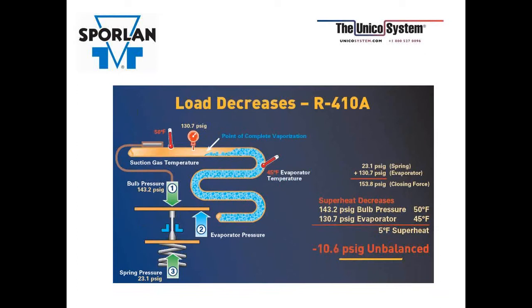And then as the load decreases, now that point of vaporization or starve point has gone beyond that last bend and is getting closer to the outlet of the evaporator, so it has less time to pick up superheat. So the bulb is going to pick up that decrease in superheat, and now it's only sensing 50 degrees. So using your PT chart, 50 degrees is going to be an opening force in the bulb of 143. Well, you have 153 in your closing force because your spring pressure and your vapor pressure are still staying the same. So now the valve is going to stroke to a more closed position, trying to find itself in that balanced state.